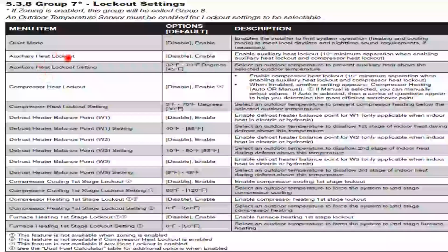We're still in lockout settings. Here's quiet mode. Keep in mind, I deleted some slides because of time, but quiet mode we want to enable. And the nighttime setback comes factory default at 0%. So that means if somebody did turn on quiet mode, then in the nighttime, it would run at its lowest setting, could be 30% or 40% depending on what unit, and therefore never heating the house up to temperature. So we've gotten complaints on that. So we do recommend going in and changing your quiet mode nighttime setback to 100%.